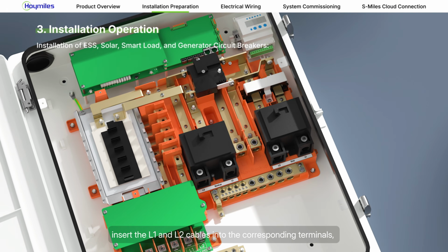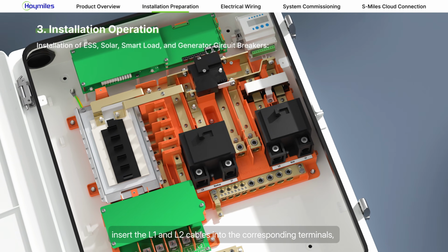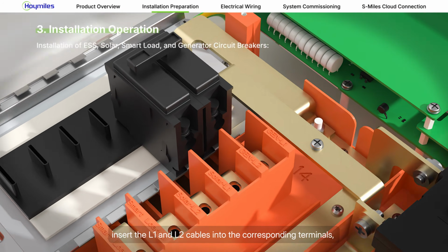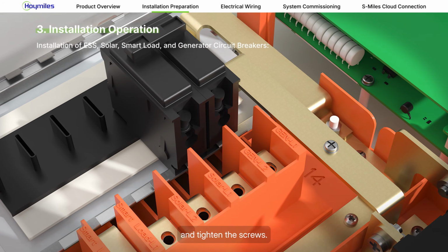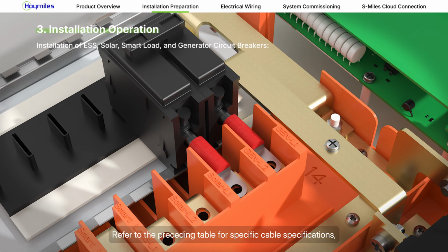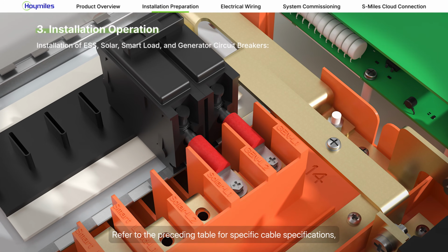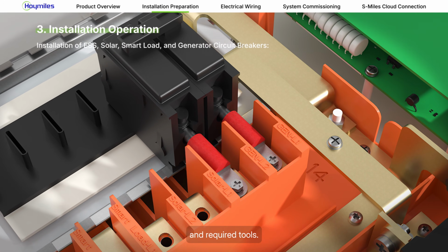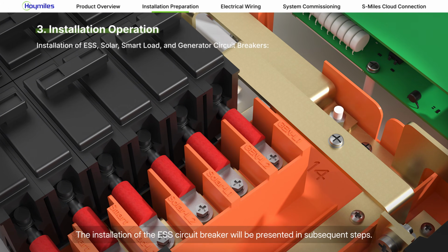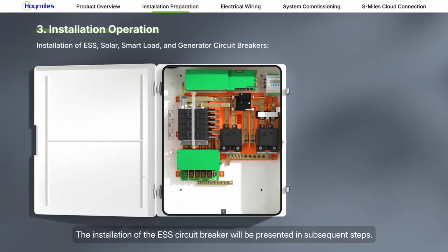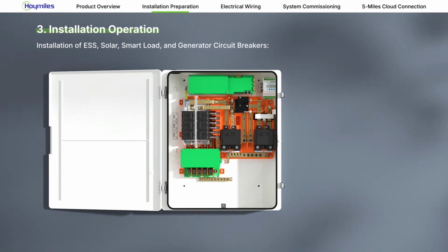Install the circuit breakers in the corresponding positions. Loosen the screws on the circuit breakers. Insert L1 and L2 cables into the corresponding terminals and tighten the screws. Refer to the preceding table for specific cable specifications, stripping lengths, torques, and requirements. The installation of the ESS circuit breaker will be presented in a subsequent step.